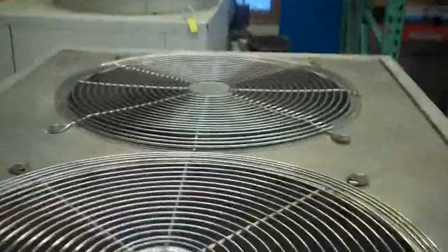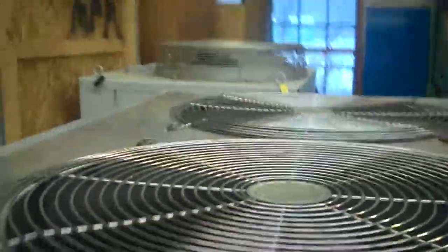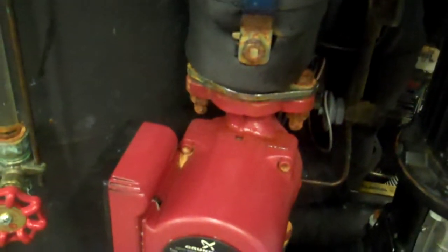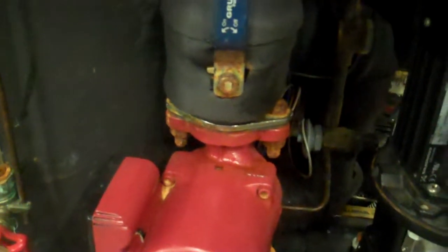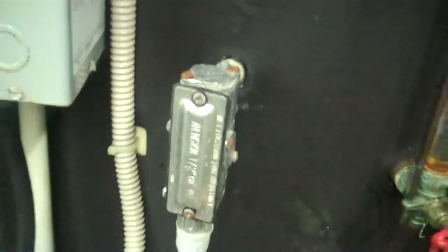This is an outdoor rated unit. It's kind of a slick unit. It's got two fans, again controlled by the variable frequency drive. It has, in addition to a Grundfos process pump here, a little smaller bypass circulation pump, which constantly ensures the right amount of flow over the heat exchanger, which is inside this insulated tank right here. This gives you the level of the fluid in the tank. This is the pressure relief. And this is the wiring that goes into an internal flow sensor.